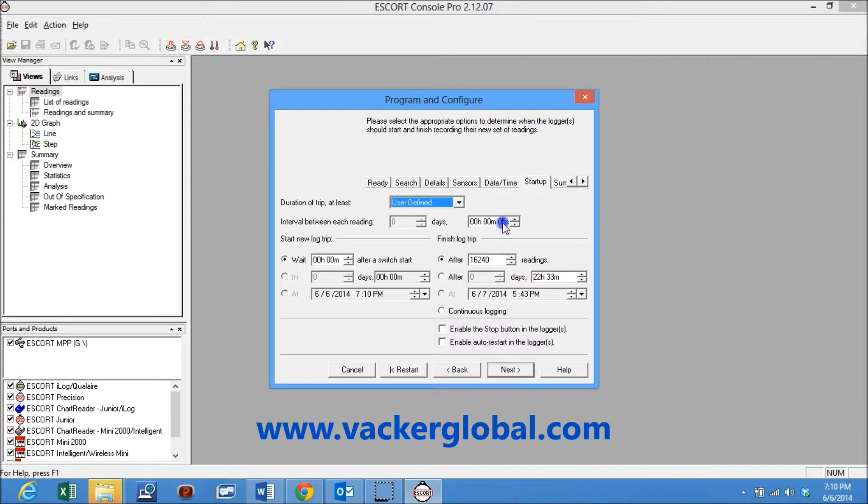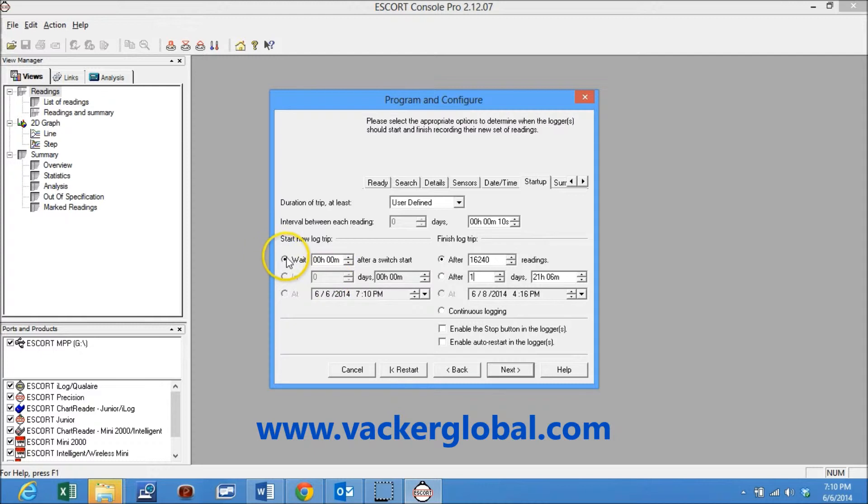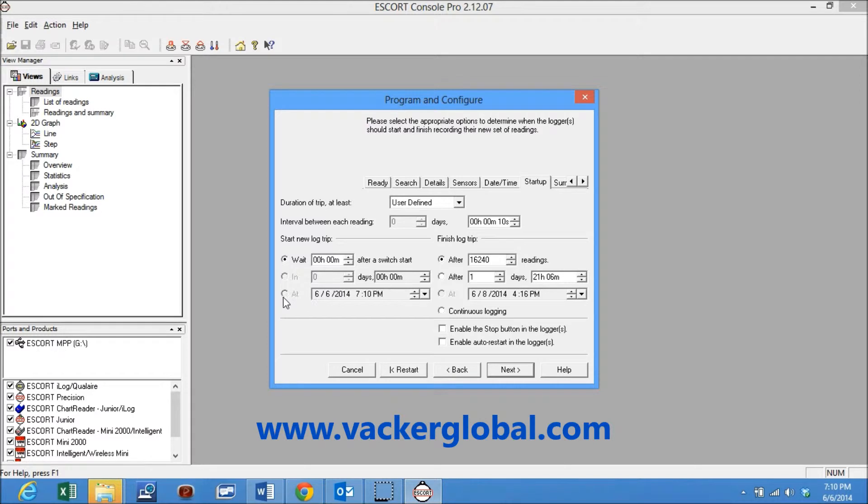The sampling interval can be programmed between 5 seconds and 18 hours. The left side is for various options on starting the recording. The right side is for options on stopping. Sampling rate of 5 seconds means data will be recorded every 5 seconds.